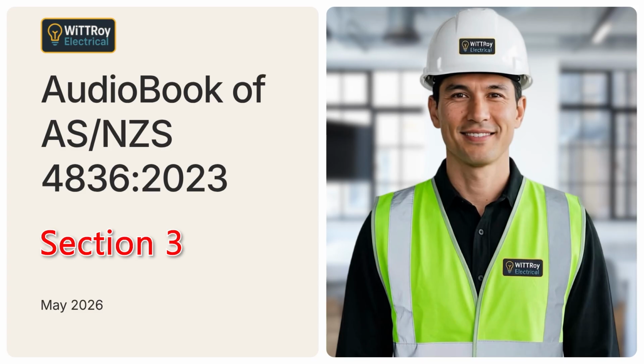3.1.4.3.2 explains danger tags. Danger tags must be placed at all points of switching, isolation, or disconnection, unless a padlock is used in accordance with the padlock requirements. A danger tag is intended to protect the individual person. In simple terms, a danger tag means someone's safety may depend on that equipment not being operated. It must not be ignored. It must not be removed casually. It must not be treated as just a general warning label.